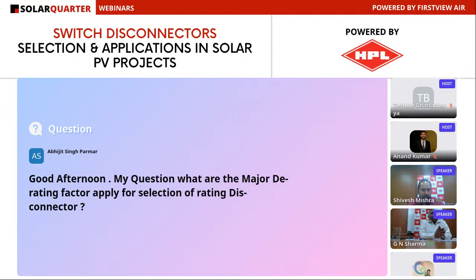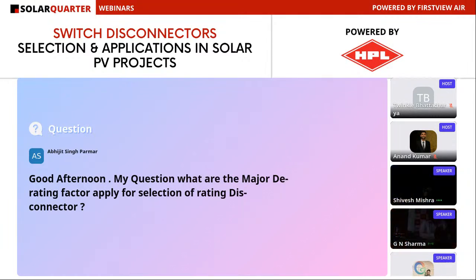The answer to this question is that when the switchgear is completely enclosed in any panel, there is a temperature rise from ambient, especially in summer areas where temperature keeps going up. There are two or three elements which create the problem: the electrical load carried by the cables, the outside temperature, and the transfer of temperature from outside the enclosure surface to inside, with no circulation of air. So the switch should be capable of handling these rated currents while keeping a gap in temperature rise, so it can do a better service. This is the reason for this.